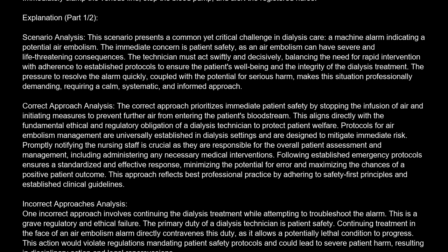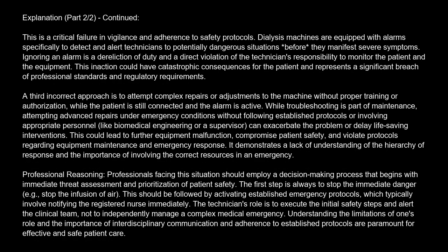Another incorrect approach is to ignore the alarm and wait for the patient to report symptoms. This is a critical failure in vigilance and adherence to safety protocols. Dialysis machines are equipped with alarms specifically to detect and alert technicians to potentially dangerous situations before they manifest severe symptoms. Ignoring an alarm is a dereliction of duty and a direct violation of the technician's responsibility to monitor the patient and the equipment. This inaction could have catastrophic consequences for the patient and represents a significant breach of professional standards and regulatory requirements.